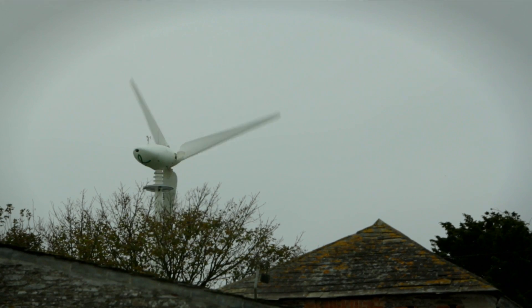The wind speed at the site of our turbine was estimated at about 6 metres per second. I asked Aeolus a couple of months ago what the wind speed had been over the last 12 months, and it was actually slightly under that — about 5.7 to 5.8 metres per second. But the turbine itself in the first 12 months had done just over 190,000 units, which we were very pleased with. That just shows that even with the average wind speed slightly down on what it would be in a normal year, we were still pleased with the result.